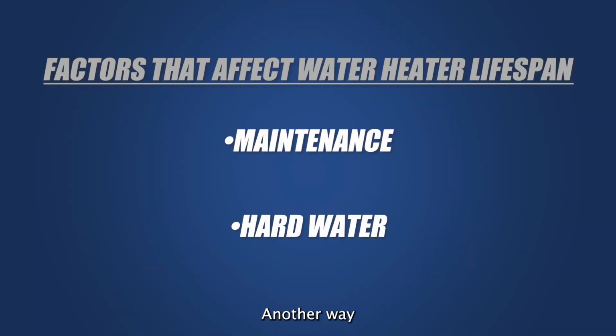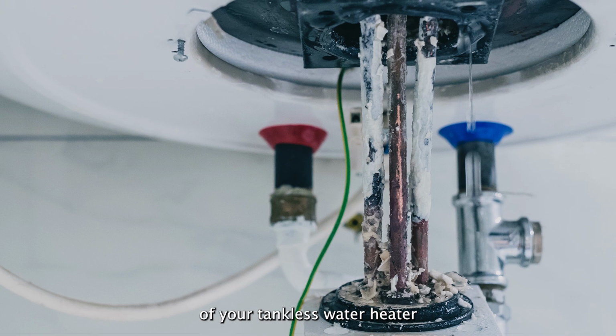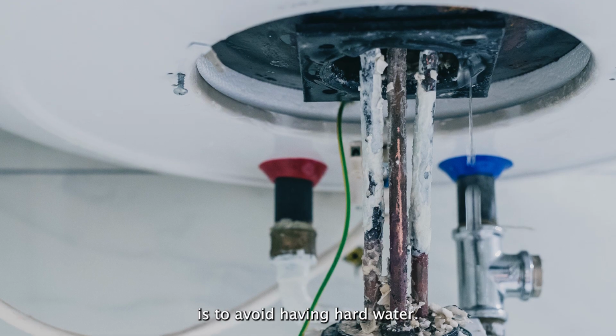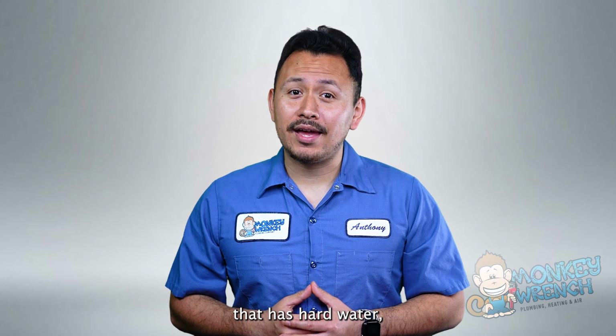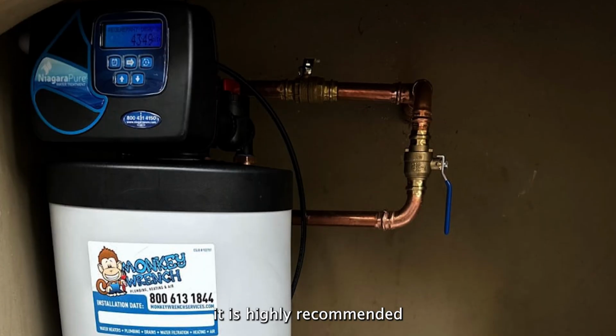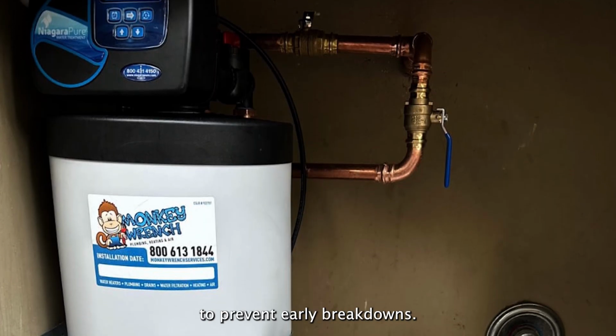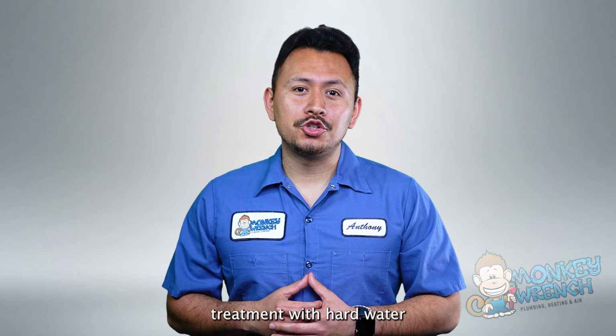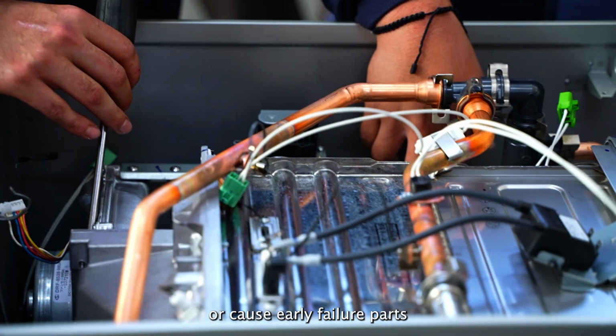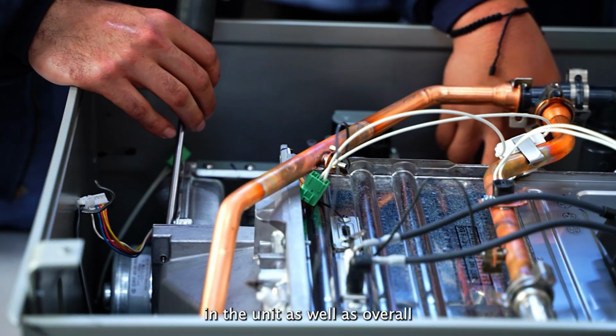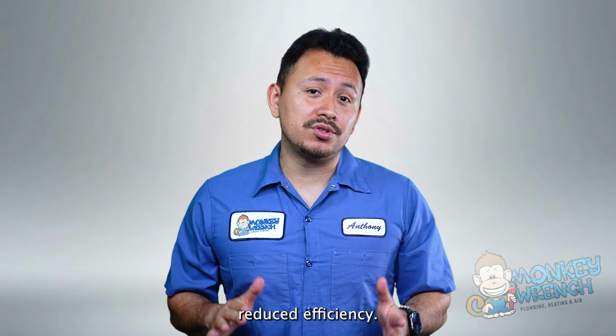Hard water: another way to prolong the life of your tankless water heater is to avoid having hard water. If you are in an area that has hard water, like much of Los Angeles, it is highly recommended that you get water treatment to prevent early breakdowns. Not having water treatment with hard water can slowly start to cause a leak in the heat exchanger or cause early part failure in the unit, as well as overall reduced efficiency.